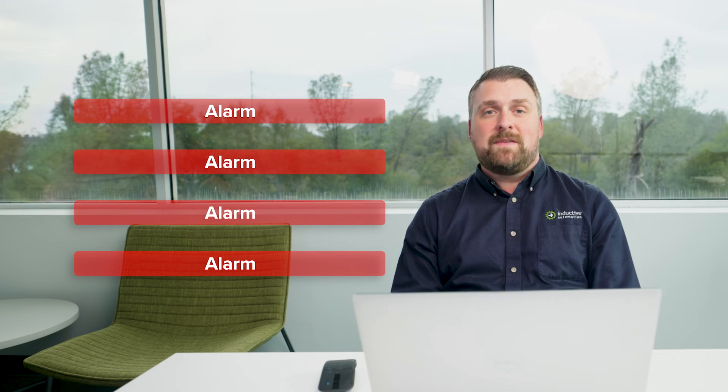The Alarm Notification module also allows you to define your own custom messages. You can do that on the pipeline level or on each alarm individually. Another really important feature is the ability to consolidate alarms. You can have a lot of alarms that occur at the same time, and instead of getting lots of individual emails or text messages, you can have one message that enumerates all the alarms that are currently active.